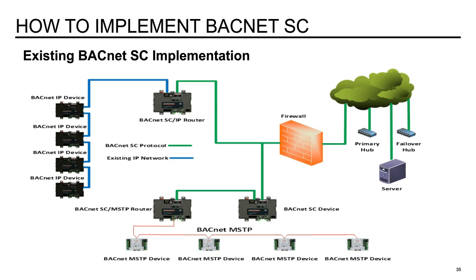And then you'll notice across the bottom, we have existing BACnet MSTP devices. And those can be added to BACnet SC by installing a BACnet SC to MSTP router. So if you'll see here, talks BACnet SC protocol. And let's say in this instance here, we were adding another air handling unit to this installation. We would simply just add another BACnet SC device on the network, and then it would talk the BACnet SC protocol, which is in green, back to the primary hub.